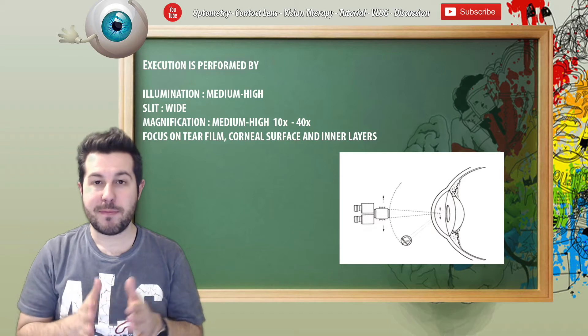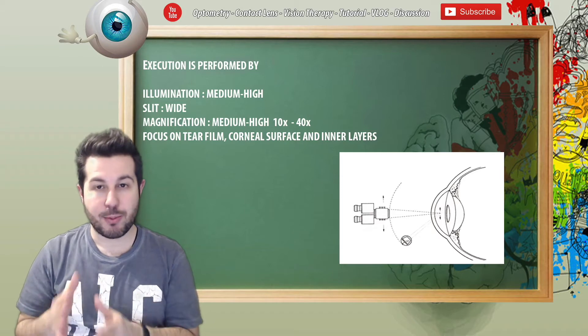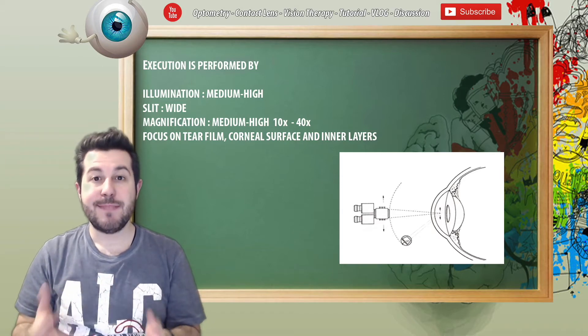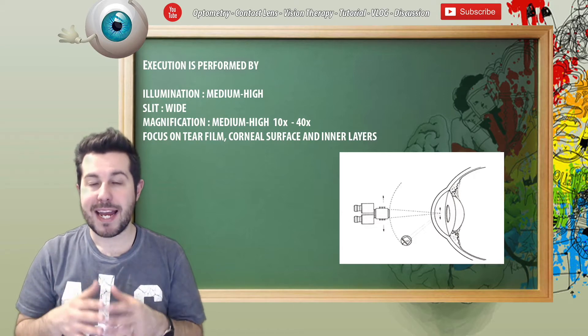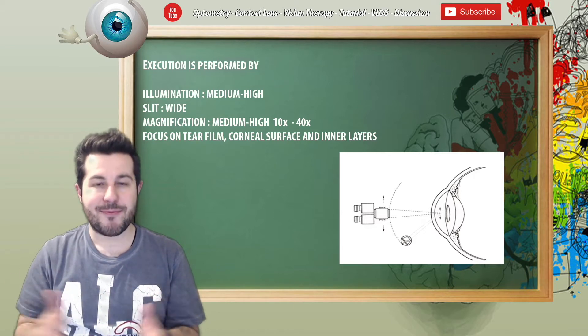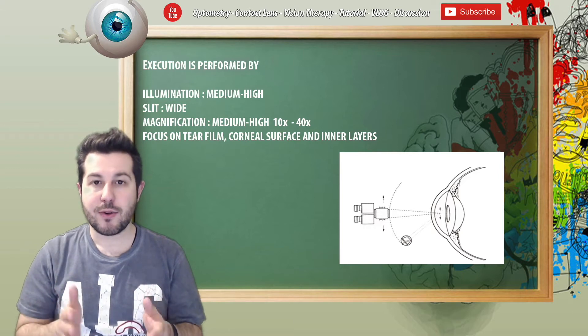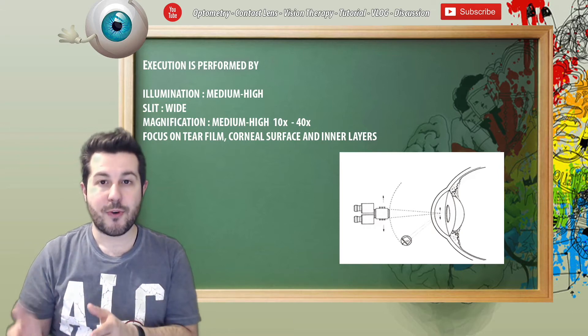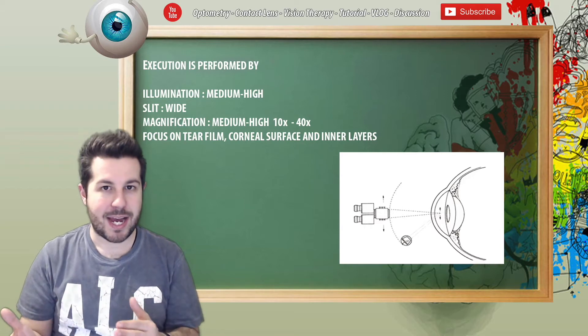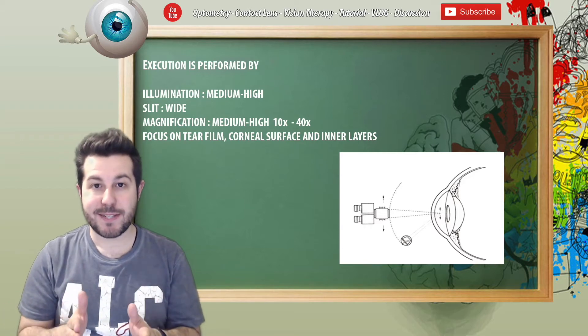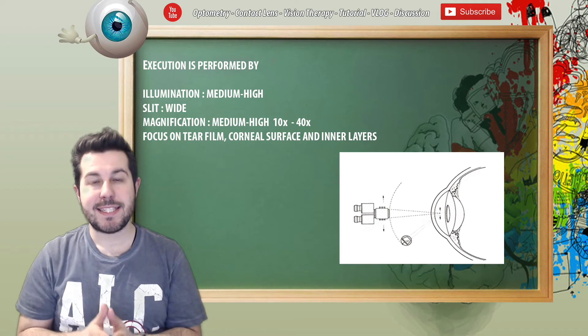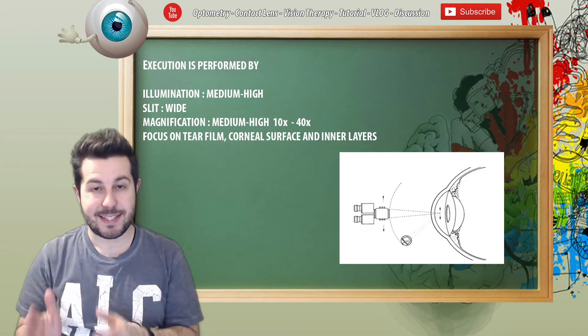The first difference between the parallelepiped and optic section is that the slit is not so tight — this allows evaluation of the cornea on a larger area. The magnification goes from 10 to 40 times, the illumination is mid to high, and the angle between the observation system and illumination system is from 30 to 60 degrees.